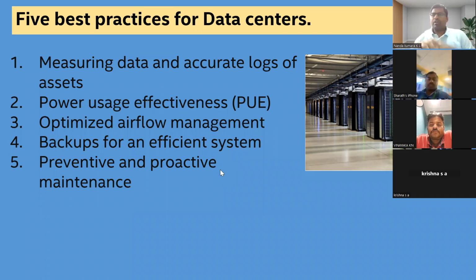Once you do the UPS thorough checking, online PM, battery load test, battery conditions, and other parameters will be checked in the UPS systems. Similarly, air conditioning units also, bi-monthly or quarterly, you have to do it. During that time, you have to check all the components in the air conditioning system, the EC fans, in case of belt drive, the belt condition, whether our sensors are showing accurate readings. There are parameters in preventive maintenance; I'll not go into depth. We all know those parameters should be thoroughly checked.